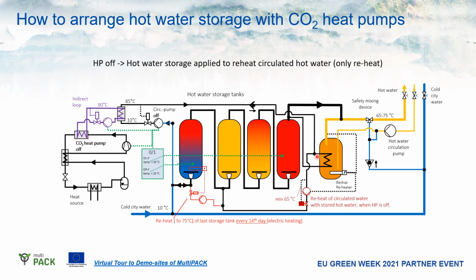This can be done by utilizing the remaining heat in the storage tanks, by applying a small circulation pump, introducing a circulation of water which is controlled to still maintain 55 degrees, for example, after this device. So we take out very hot water. Remember, 75-degree water from the tank is circulated the other way around in this heat exchanger, reheating the water which is circulated and pushing this water into the second last tank.